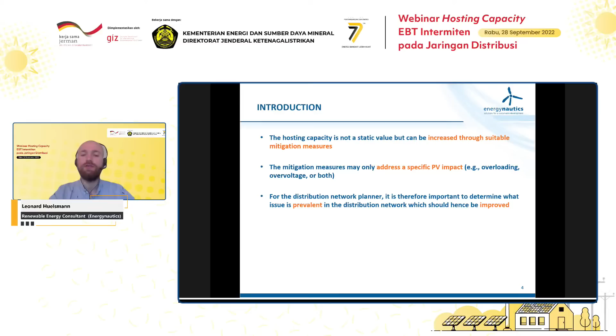These mitigation measures may only address a specific impact of distributed generation, for example, only overloading or only overvoltage. And so for the distribution network planner, so for people from the utility, for people from PLN, it's important to understand how different mitigation measures will impact or address the PV impact and improve the situation of distributed generation. Generally, there are a lot of mitigation measures that you have available, but it needs technical understanding in order to figure out what are good measures, what exactly will they do and how will they impact this.